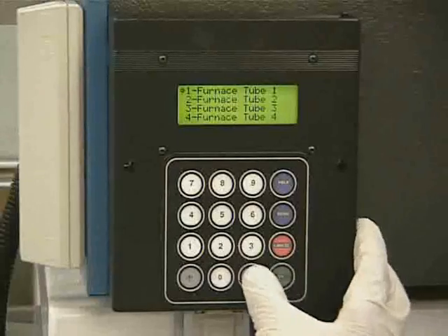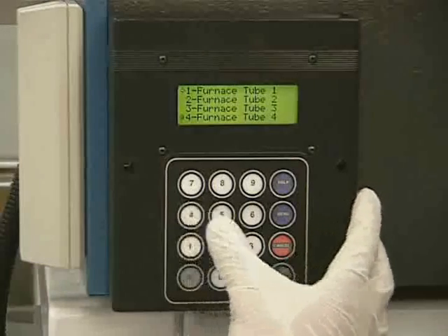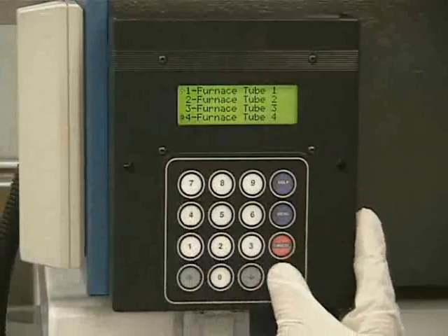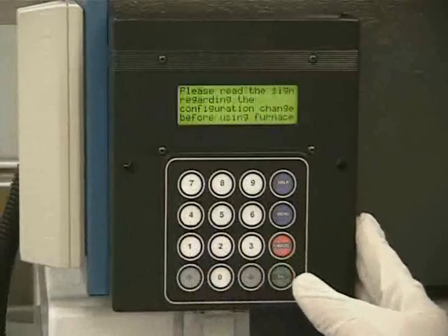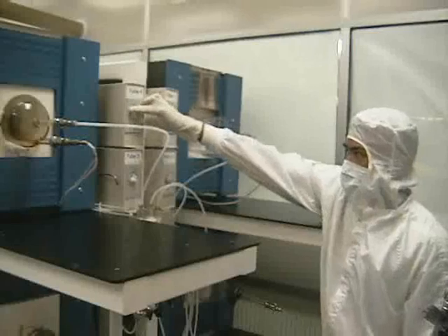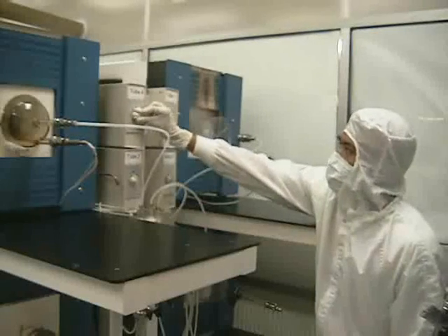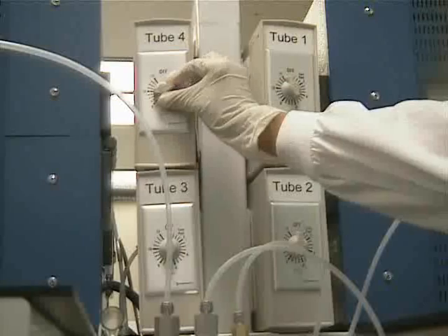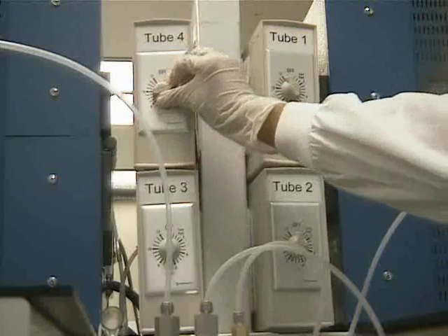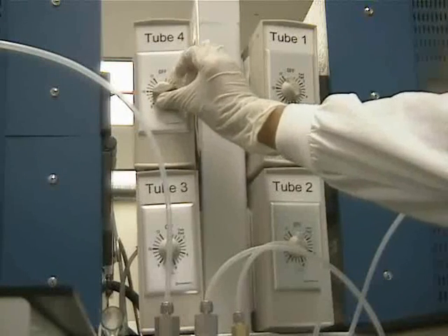When you log into the Lindbergh Furnace, select the furnace tube you are going to use for your process. The first step in setting the atmosphere is to set the gas flow timer to the length of your run. This will prevent the waste of gas in the system when the tube sits idle at the end of the run.